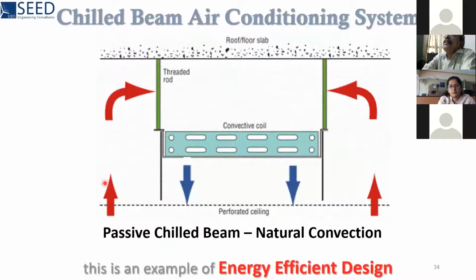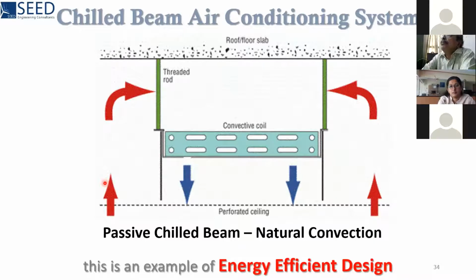Now we are going to understand what is meant by a chilled beam system of air conditioning. A chilled beam is nothing but a cooling coil similar to the radiator of a car, but slightly bigger in size. The hot air in the room rises to the top, and when it passes through the cooling coil, it gets cooled, and cold air comes down, hot air goes up, again passes through the cooling coil, so that air is cooled by a process of natural convection, so that it is known as a passive chilled beam.